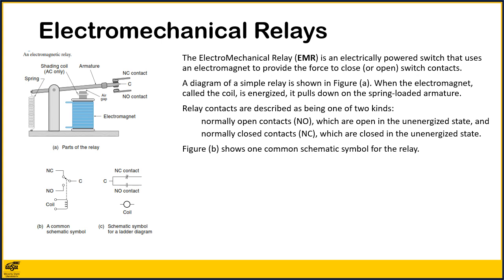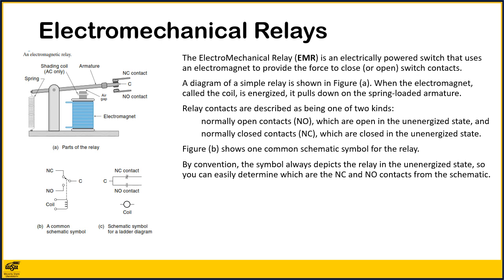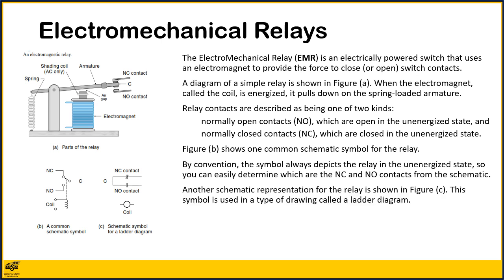Figure B shows one common schematic symbol for the relay. By convention, the symbol always depicts the relay in the unenergized state, so you can easily determine which are the normally closed and normally open contacts from the schematic. Another schematic representation for the relay is shown in Figure C. This symbol is used in a type of drawing called a ladder diagram. In a ladder diagram, the relay coil and its contacts are separated on the drawing. We will see more about ladder diagrams in chapters 9 and 12.